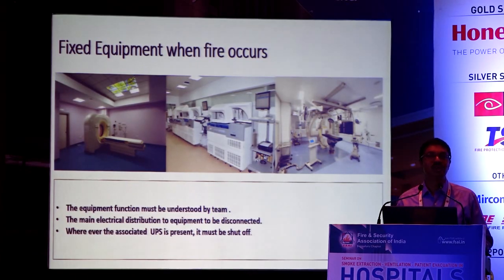MRI works on a strong magnetic field, so a person entering the MRI should be away from magnetic things. When a mishap happens, we need to ensure they are evacuated properly, and an MR compatible fire extinguisher has to be used. This is something that needs to be known.